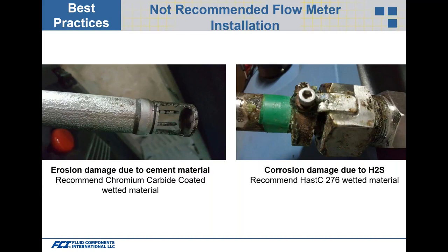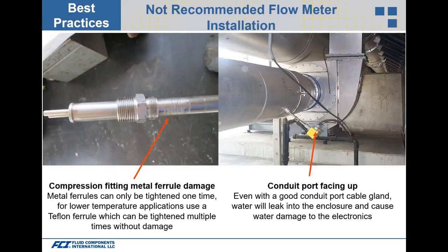Erosion damage from cement or abrasive material can degrade the probe — some manufacturers offer a chromium carbide coating for protection against erosion. Corrosion damage from H2S (hydrogen sulfide) requires Hastelloy C wetted material — it's critical to understand the process gas composition and select compatible flow element materials. For process connections using compression fittings: Teflon ferrules can be removed and reinstalled repeatedly at lower temperatures, but metal ferrules should only be crimped once to avoid probe damage.